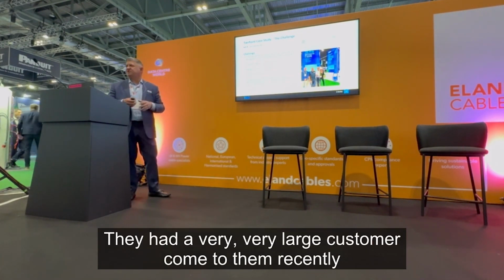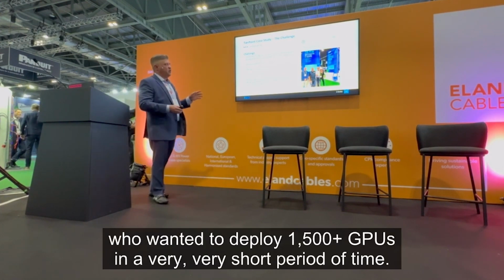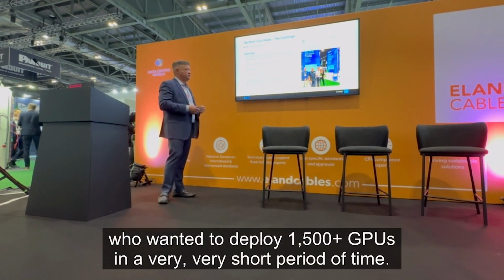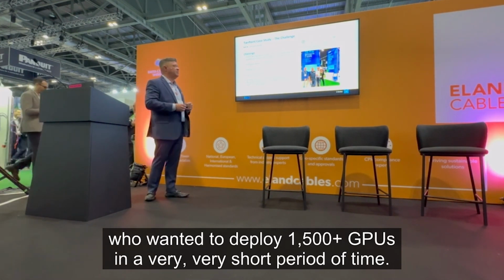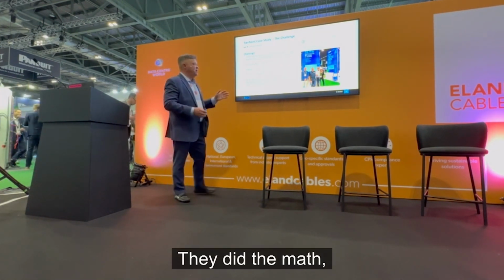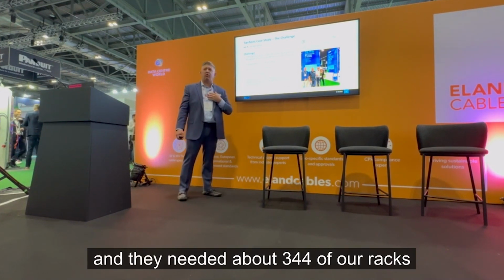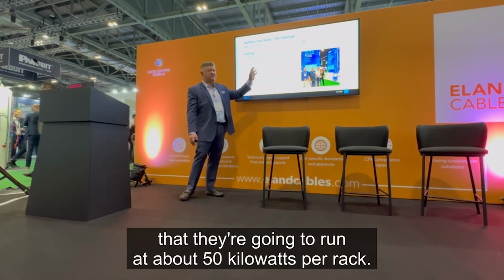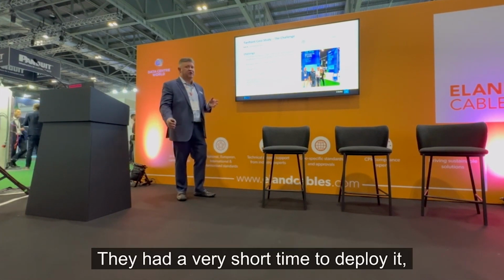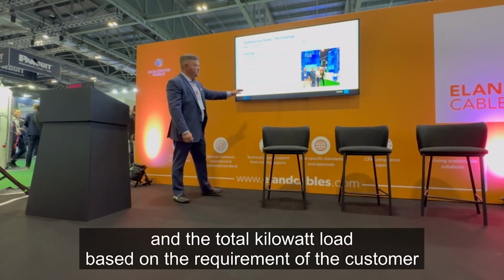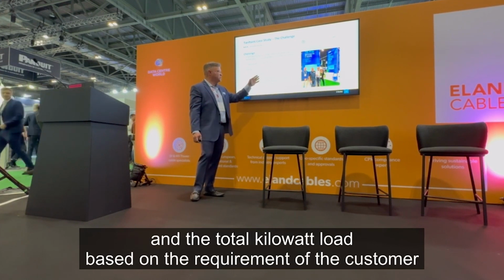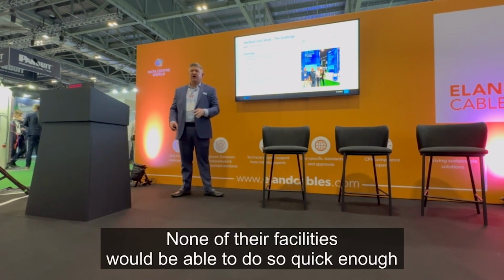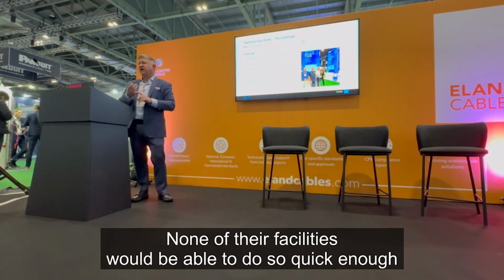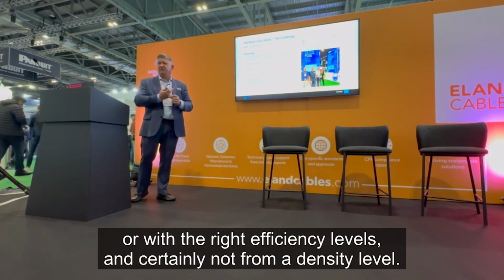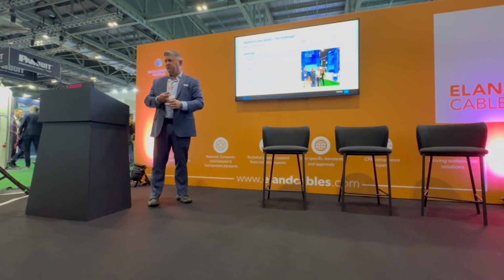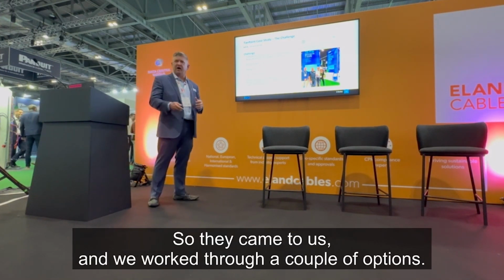They had a very large customer come to them recently who wanted to deploy 1,500 plus GPUs in a very short period of time. They did the math and needed about 324 of our racks running at about 50 kilowatts per rack. They had a very short time to deploy it, and the total kilowatt load based on the customer's requirement was 16 megawatts. In none of their facilities were they able to do so quick enough, with the right efficiency levels, or certainly the right density level. So they came to us and we worked through a couple of options.